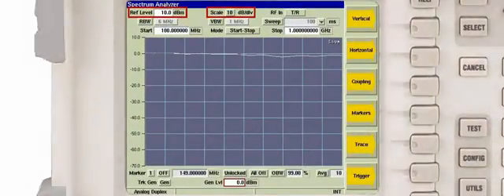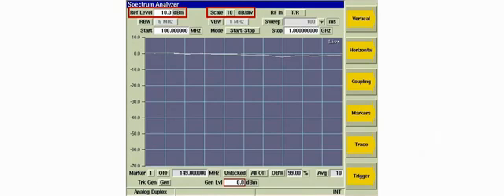If the trace is not visible on the display, set the scale for 10 dB per division and adjust the reference level until it can be observed.